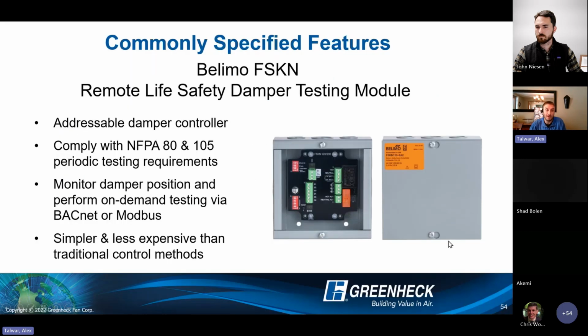Yeah, I don't want to go too deep into installation stuff, but this is something worth talking about. This is something Belimo, at least, just brought to the market. This is the FSKN. It's an addressable damper controller, BACnet compatible, and you can basically just hook this right up to the building automation system and use it to perform your periodic testing requirements. It avoids some of the contractor costs possibly of hooking up all these addressable systems. It's pretty new to the industry, so it's still taking off, but I think it's going to really start becoming a commonly seen feature on these fire smoke dampers.